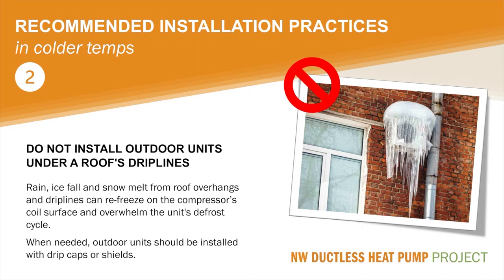Next up, do not install outdoor units under a roof's drip line. Rain, icefall, and snow melt from roof overhangs and drip lines can refreeze on the compressor's coil surface and overwhelm the unit's defrost cycle. If possible, outdoor units should be installed outside of the roof's drip line.